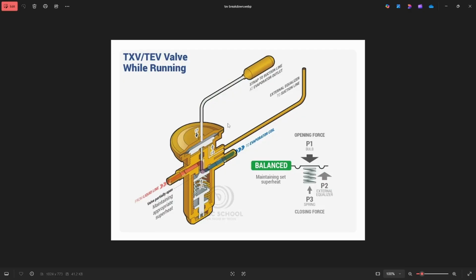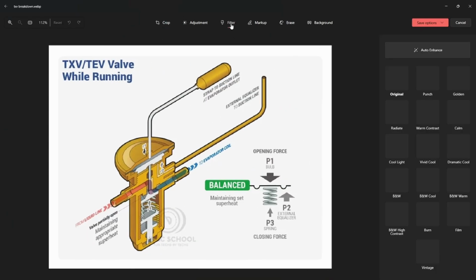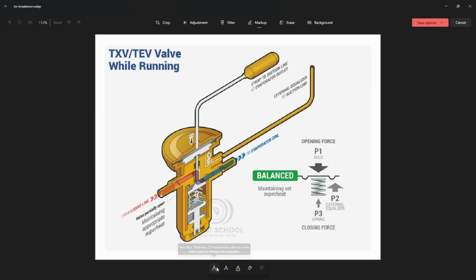But I'll start this by reviewing what the parts of a TXV are, and then we'll go into an EEV and what makes it different, why we would use an EEV over a TXV, and then some basic troubleshooting stuff for EEVs that differ from TXVs. So, a TXV or a TEV is a thermostatic expansion valve. We know that. So, with thermostatic expansion valves, we have a couple different forces acting on our diaphragm and on the power head.